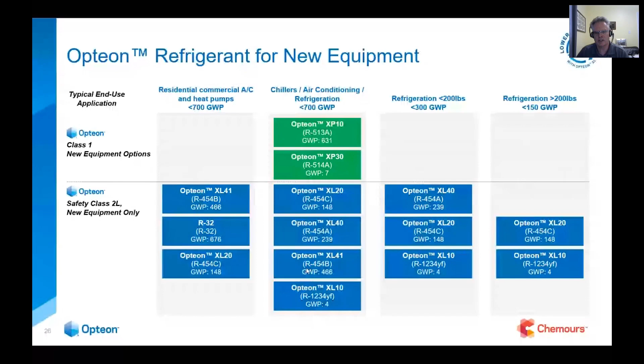Less than 300, when that's required, in most cases it's likely going to transition to 454A or XL40. And that 454A really looks like 404A. And I think the condensing unit manufacturers are migrating this way because of the refrigeration capacities and the design similarities to 404A systems. When we look at 454C, it really kind of has the capacity of R22, and the decision factor is going to be, when do I need less than 150 GWP? And that's where we may see more of a trend towards this, particularly in the larger systems.